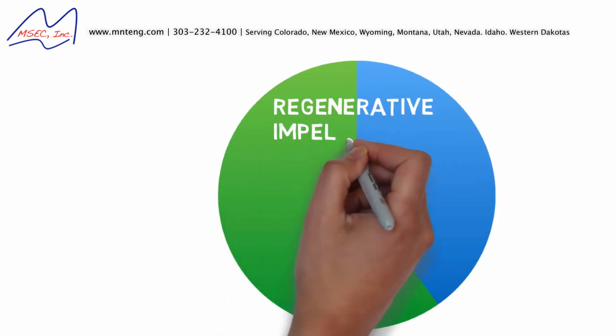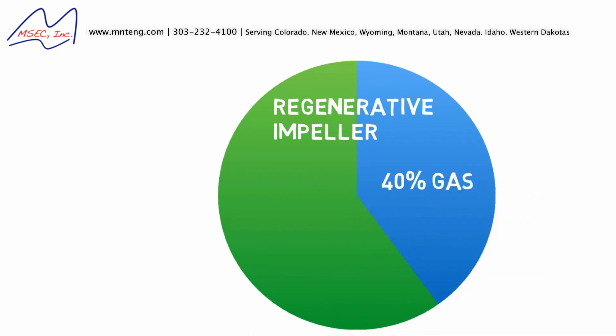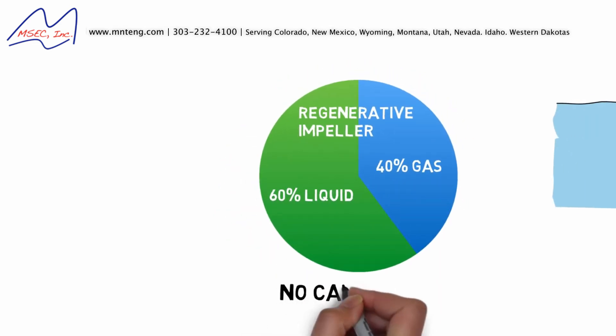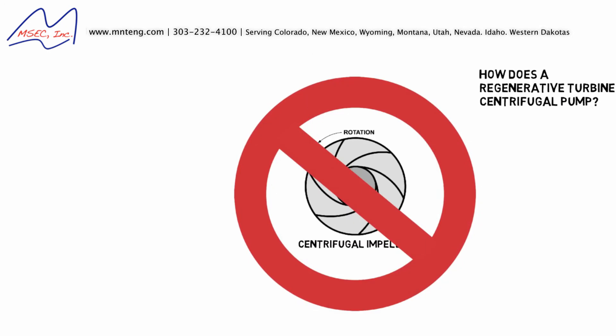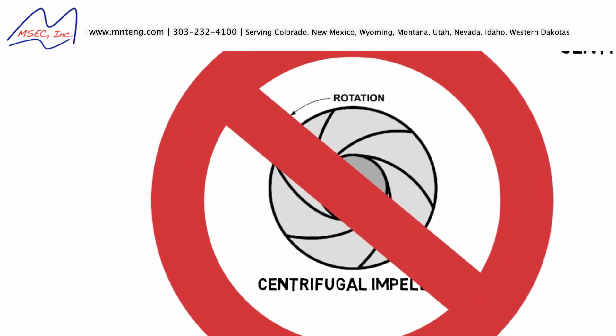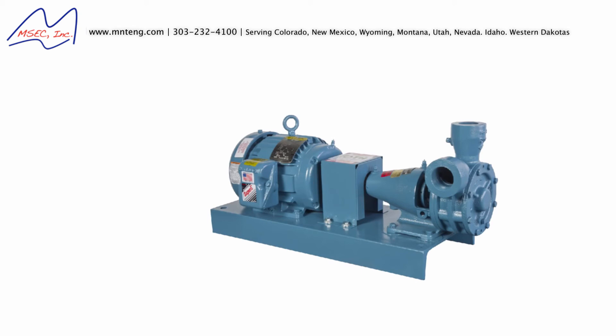The regenerative turbine impeller can pump fluid with up to 40% entrained gases without damage from cavitation or any performance loss. Centrifugal pumps are not designed to handle gas in a liquid. Gas in a centrifugal pump can create a significant loss in performance, causing fluctuating flow, discharge pressure, and unnecessary wear and vibration of the centrifugal pump's internal components. This makes a regenerative turbine pump a great solution where cavitation is a concern.